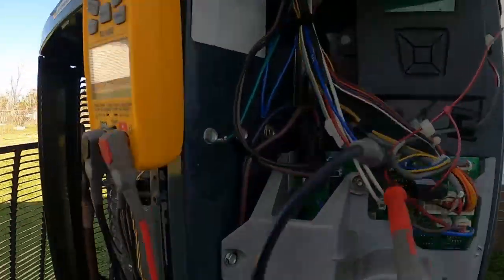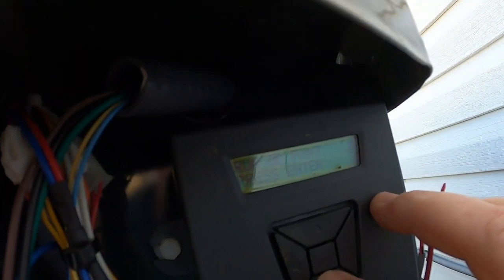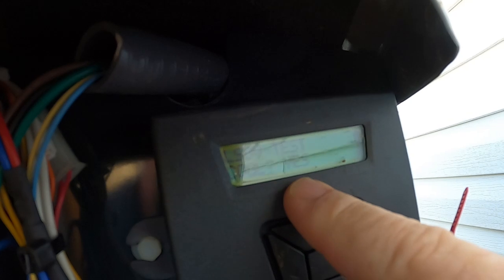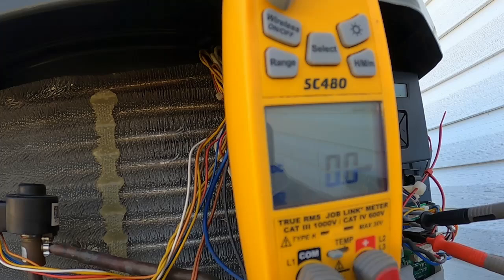I'll reverse it now. Getting the leads in there — sometimes it's a little difficult to get a good connection. That little white plug with the red and blue wire is the one coming off the reversing valve. We're going to go over here and run the RV test — there's our switchover valve test. Right now it's in cooling. I want to run the test, yes. The test is in progress.